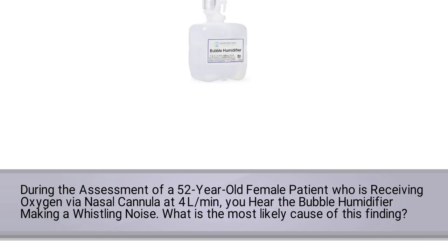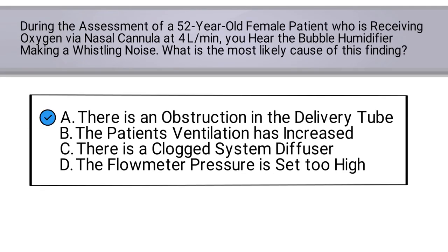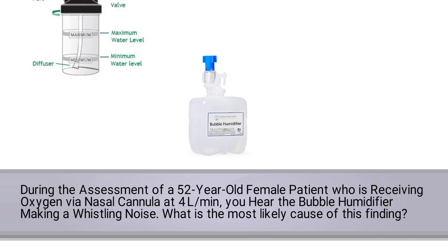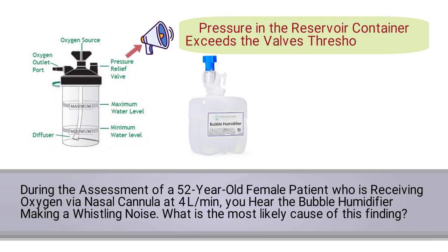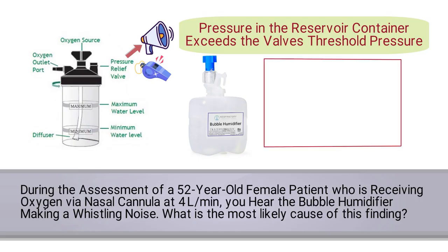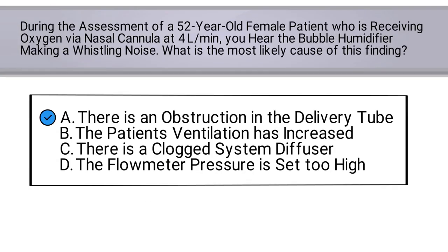If you've ever accidentally stepped on the tubing of a bubble humidifier while it's being used, you will automatically recognize that the correct answer is A. The relief valve of a bubble humidifier was designed to sound whenever the pressure in the reservoir container exceeds the valve's threshold pressure, resulting in a loud whistling noise. The most common reason for this to occur is when there is a downstream obstruction to outflow. This one was short and sweet because there is clearly only one possible correct answer, and it's A: there is an obstruction in the delivery tube.